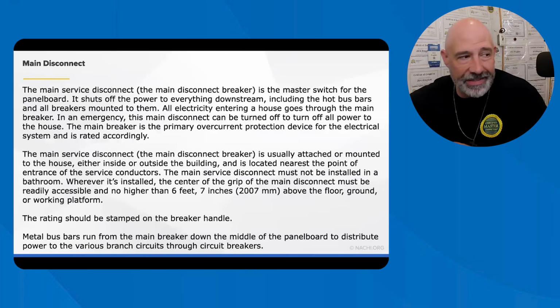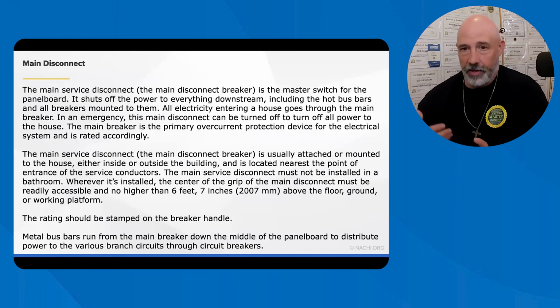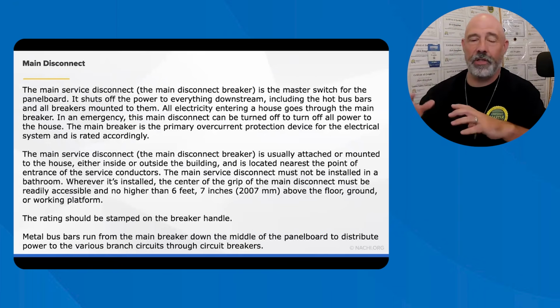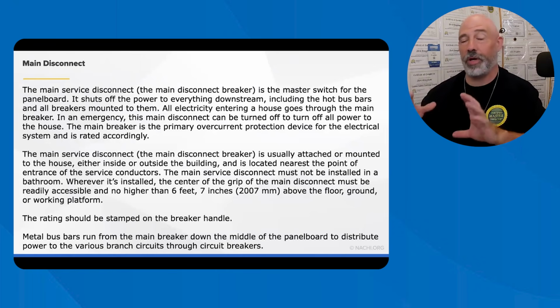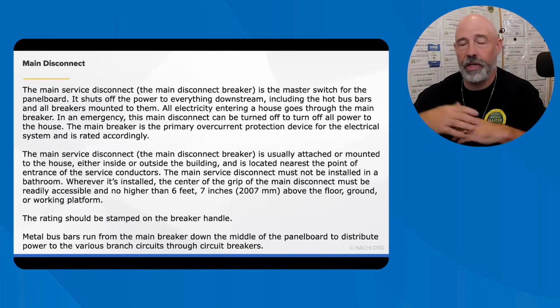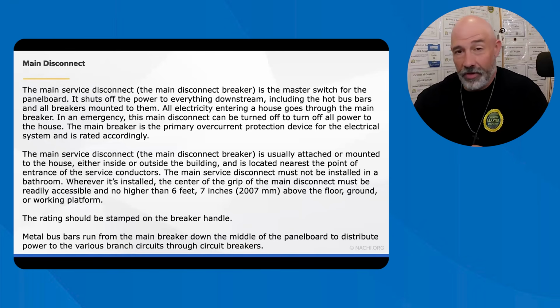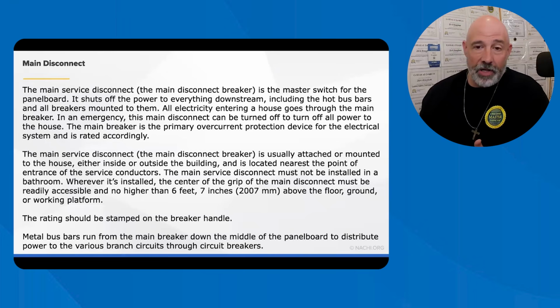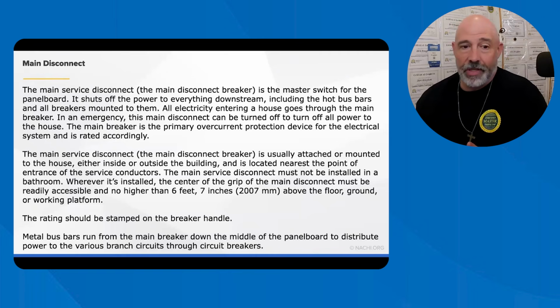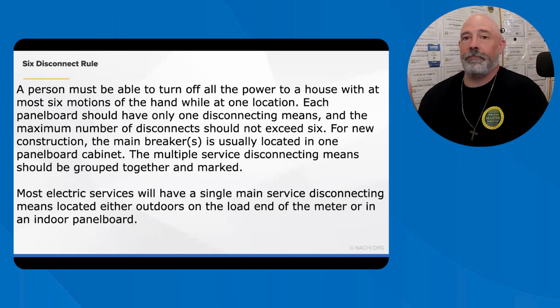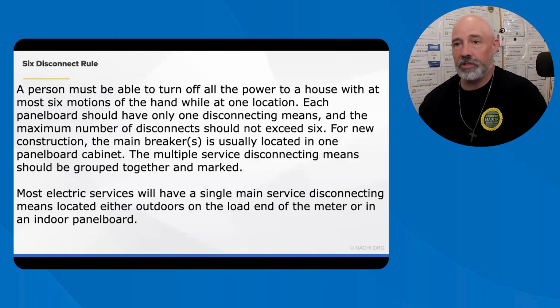Okay. The main service disconnect, or the main master panel or the master switch of the home, is the overcurrent protection device. It is typically located outside now, and it's where the service enters into the house. We want the main breaker outside, because if there was a fire, the fire department can go in there and just shut it off. It must be readily accessible and no higher than 6 feet 7 inches above the floor grade. So the main breaker feeds the bus bars, which distribute the power to the home's branch circuits. A person must be able to turn off the power to a house in at most 6 motions. So 1, 2, 3, 4, 5, 6. Boom, easy. Do not exceed that 6.